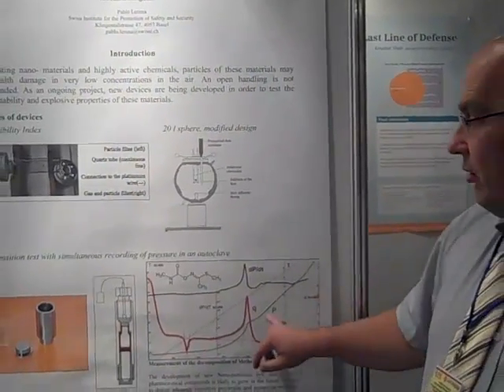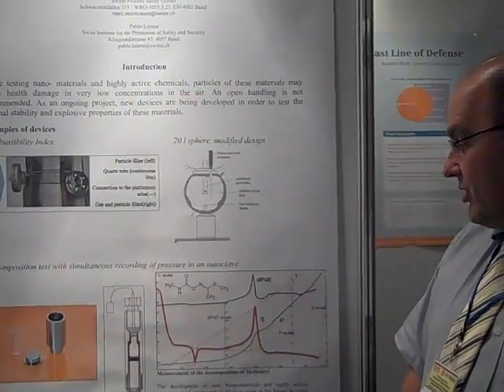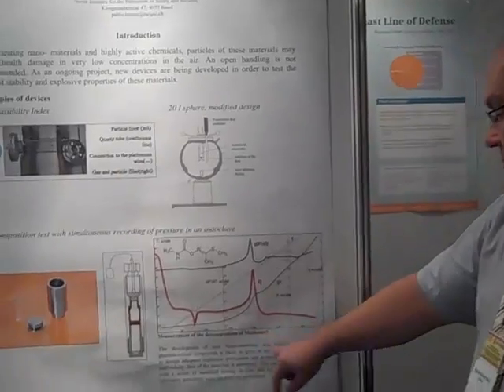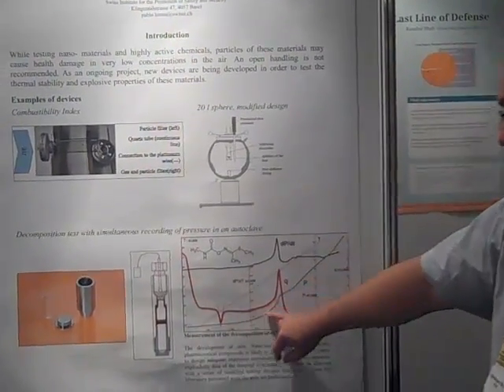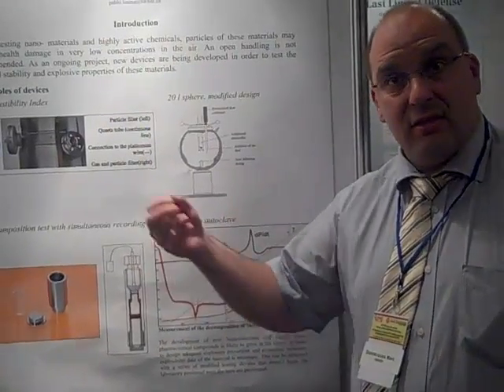The third device is for decomposition tests. In one of our crucibles — a Setaram C80 calorimetry crucible — we fill in the substance, also using a glove box, and then we perform decomposition tests. For example, with a given substance you can see here the heat capacity and here the decomposition. We can also measure the pressure directly, and afterwards we collect the decomposition gases and analyze them by chromatography.